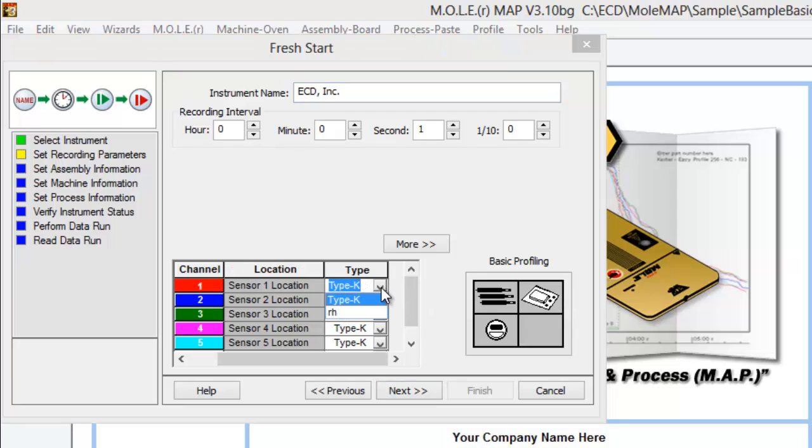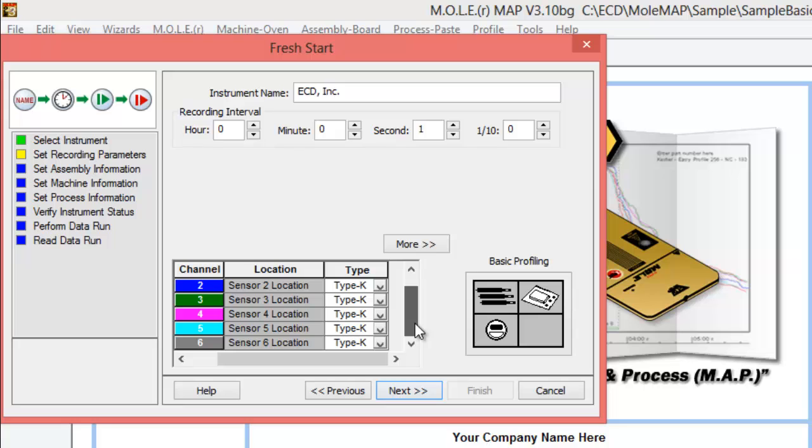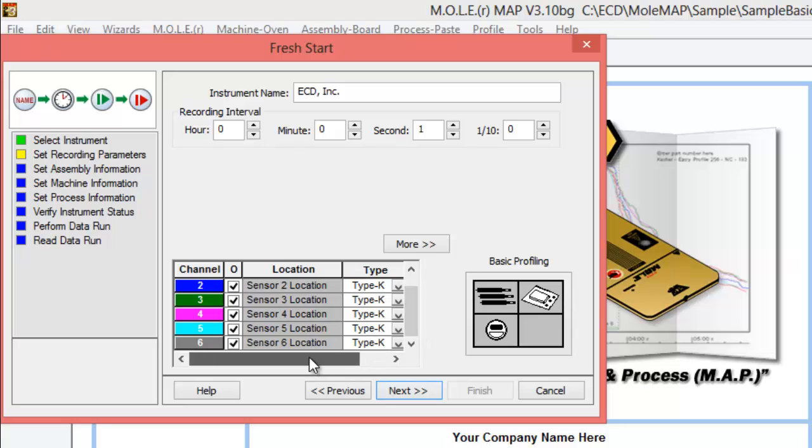Our thermocouples are set up for type K. You'd only really change this if you had one of our MiniMole products, which measures relative humidity as well. Now that we've named our instrument and selected the logging rate, made sure we got all our channels turned on here.